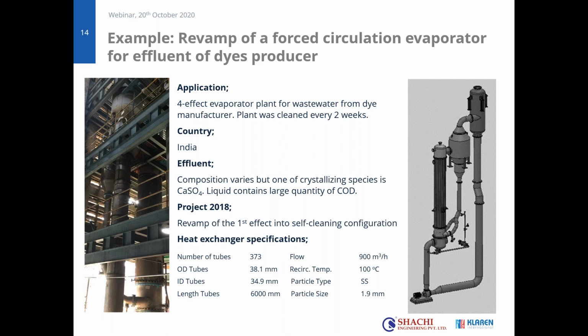In this case, we were also a bit lucky because it was a 3-pass heat exchanger. Since we reduced the tube velocities and would like to have a comparable flow, if you reduce the tube velocity and you want the same flow, you need more tubes. But since it was a 3-pass, we could convert the 3-pass into a single pass. By doing that, you would need 3 times the number of tubes to have the same flow. So that was a nice coincidence, which resulted in an easy revamp in terms of the process conditions.